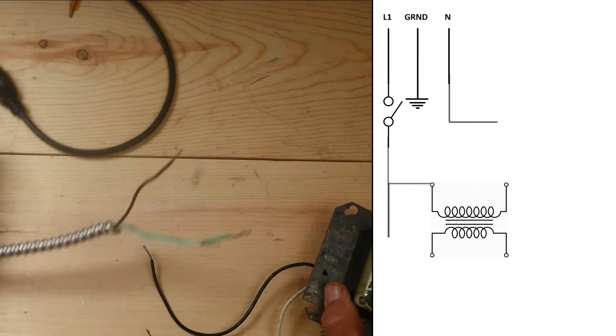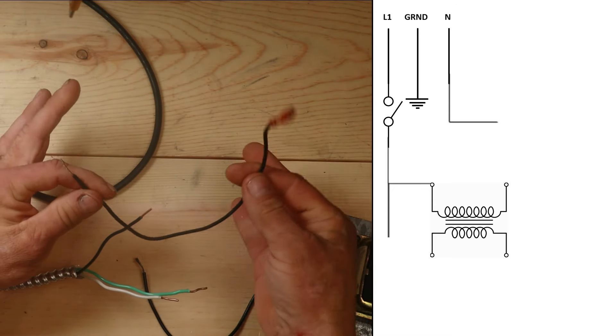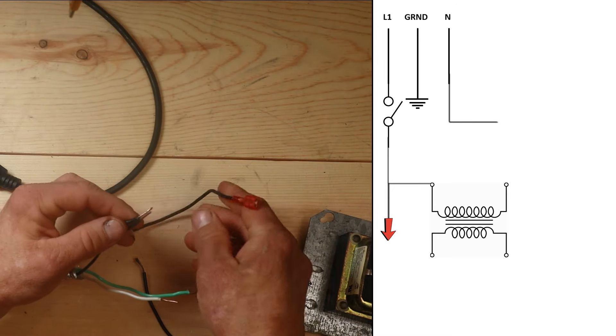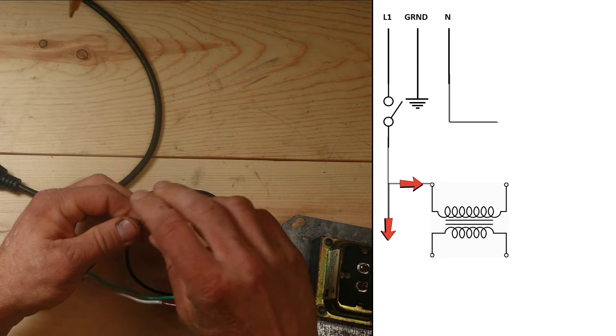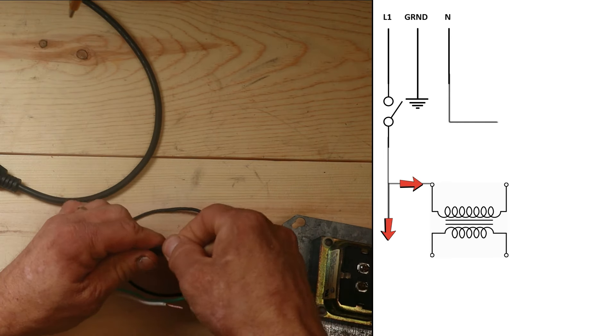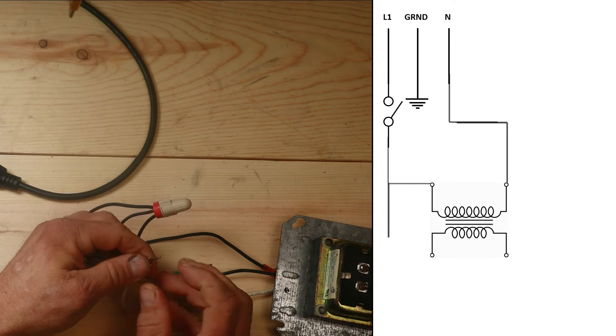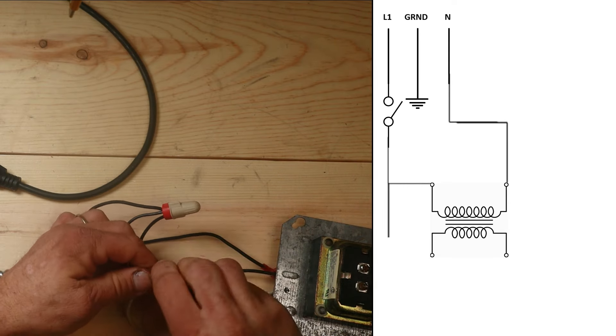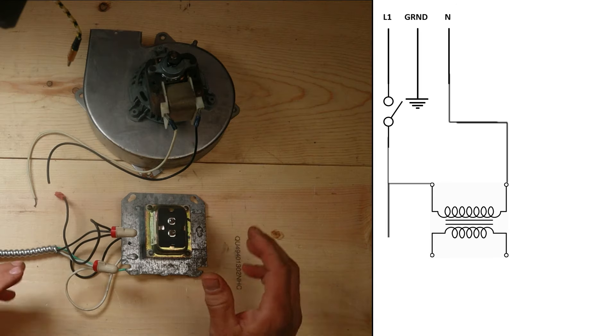If you do a continuity or resistance reading and you're reading open line, you pretty much have a blown transformer. So we're going to take our wire carrying high voltage to our motors, and the black wire connecting to our low-voltage circuit, and wire-nut those together. Then we take the neutral from our transformer back to neutral, which goes back to our switch and to the electrical panel.